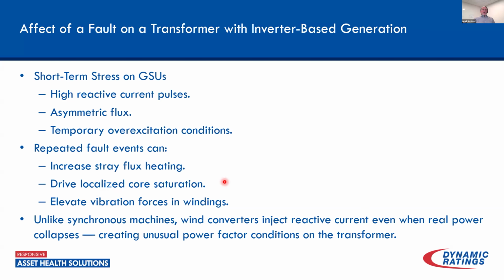So again, the key component here is, unlike synchronous machines, the inverter-based resources are injecting reactive current, they're responding to the events and so on. Now, some of this depends on what the requirements are for the ISO, because if we look at the fault on the Iberian Peninsula, or the blackouts in that situation, there they had a little different situation. There, they basically required that the power they're producing had to be at unity power factor. So they're power factor limited.